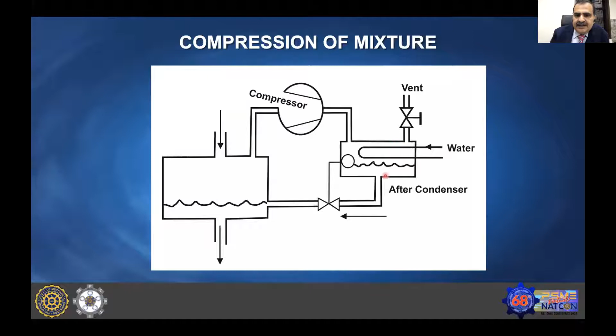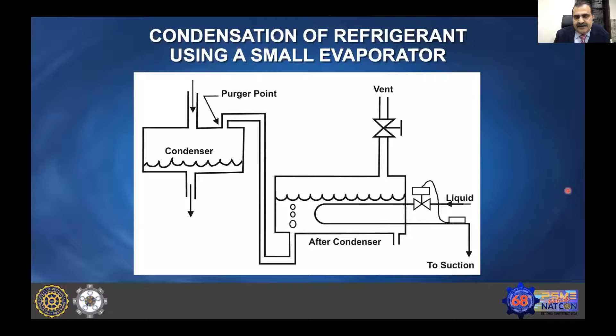The second type of system uses the refrigerant from the refrigeration system. You have a heat exchanger here, which is cooled down to minus 7 degrees centigrade minimum, and your purge point from the condenser or receiver is brought into contact with this coil. If there is ammonia, it condenses and becomes liquid, and it is taken back. If there are non-condensables, you can vent them out. This can be done automatically by using proper sensors, such as ammonia sensors, for sensing the temperature and pressure difference in the vessel.